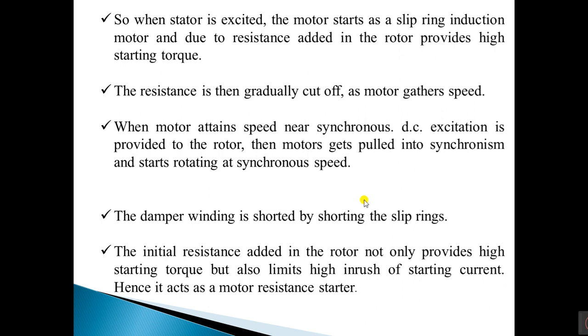So here also the damper winding is short circuited by shorting the slip rings. The initial resistance added in the rotor not only provides high starting torque but also limits the high inrush current at starting. Hence it acts as a motor starting resistance.